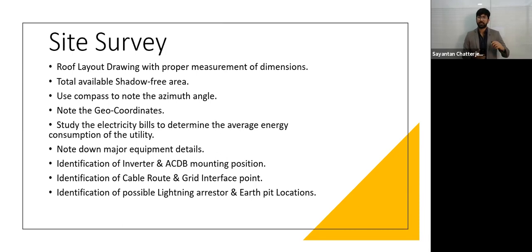After the site survey, we generally study the electricity bills to determine the average energy consumption of the utility. If we can get 12 months of electricity bills, that's best. If not, we need at least 2 summer and 2 winter months, because in summer energy consumption is very high, and in winter it comes to a very low level. For designing a solar power plant with proper capacity, we need to analyze this energy consumption pattern, and we usually note down the major equipment details.